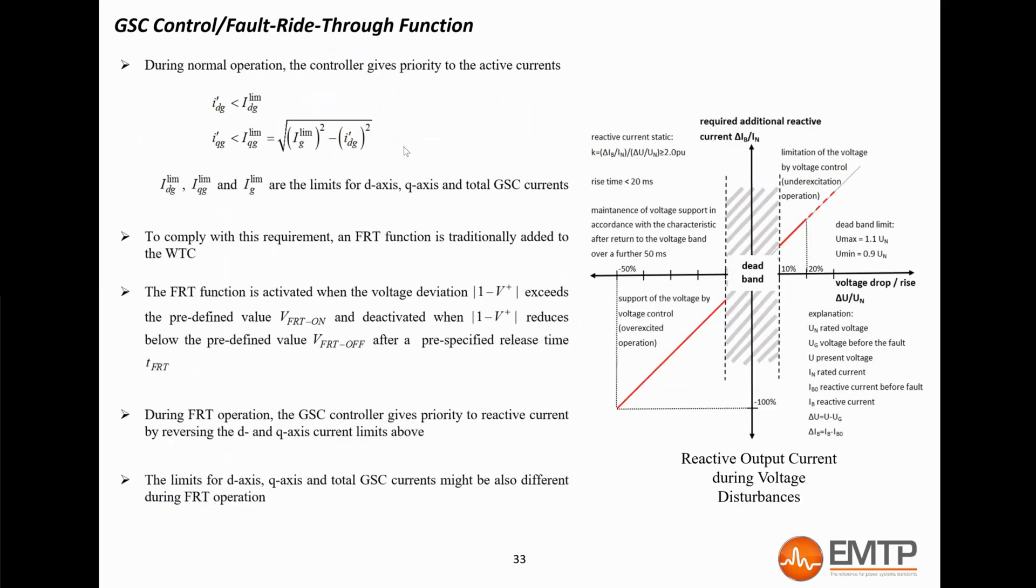Let's now explain the limiter device of the grid-side converter. During normal operation, the controller gives priority to the d-axis current, which corresponds to the active power. The wind turbines are equipped with a FRT function to fulfill the grid code requirement regarding voltage support. The FRT function is activated when the voltage deviation is above a user-defined threshold and is deactivated when the deviation goes back below a reset threshold. When the FRT function is active, the grid-side controller gives priority to the reactive power current.